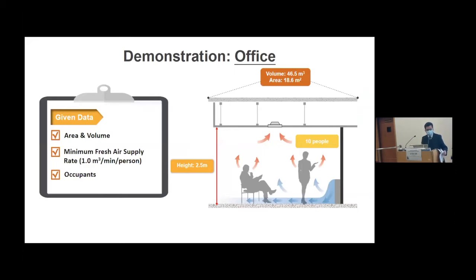So to give you a feeling of what these numbers represent, let me work out a very simple calculation. Let's take a conference room of 200 square feet with 10 people occupying it as an example. The 200 square feet, with a simple conversion, works out to approximately 18.6 square meters. Assuming a normal office ceiling height of 2.5 meters, the volume of the occupied space is approximately 46.5 cubic meters. With 10 people in the conference room, the minimum fresh air supply rate, in accordance with the aforesaid regulations, is 10 cubic meters per minute. That is equivalent to 600 cubic meters per hour.